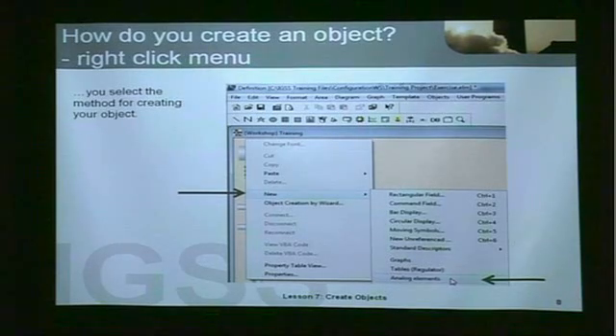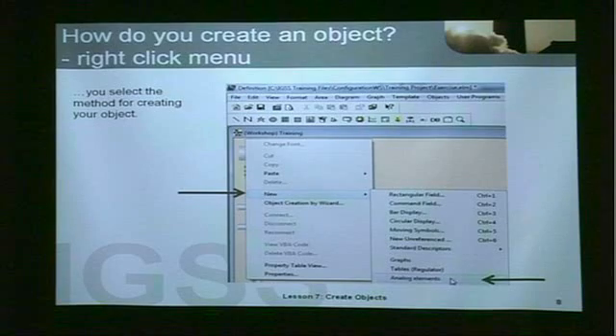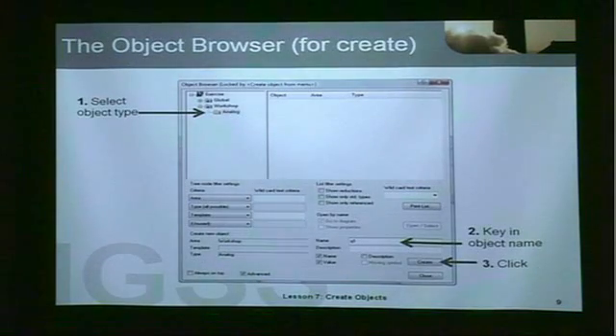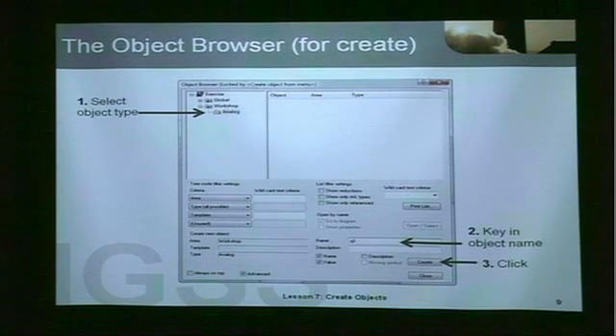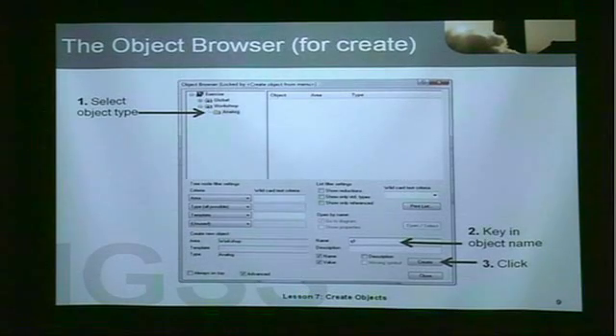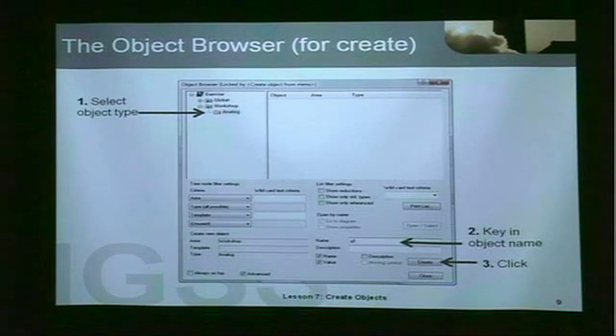In this case, we're creating an analog object because we've chosen the last menu item in the right-click menu called Analog Elements. No matter which method you use, the next thing that will occur is that the object browser will appear. Notice the title at the top of the dialog box: 'Object Browser locked by create object from menu' — so you can look up there to find out which method you've chosen to create your object. The next thing is to make sure you select the correct area, which in this case is Workshop.